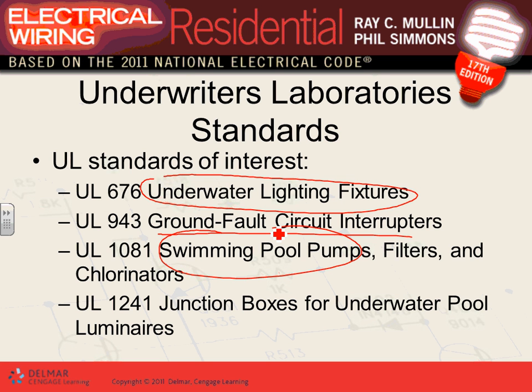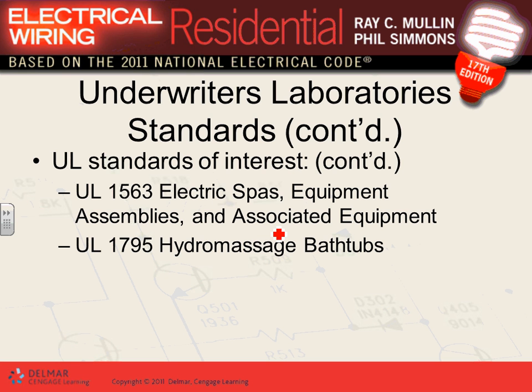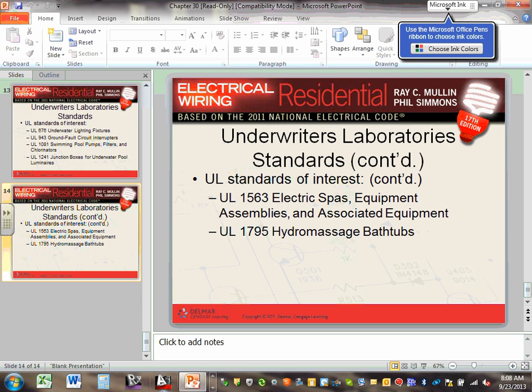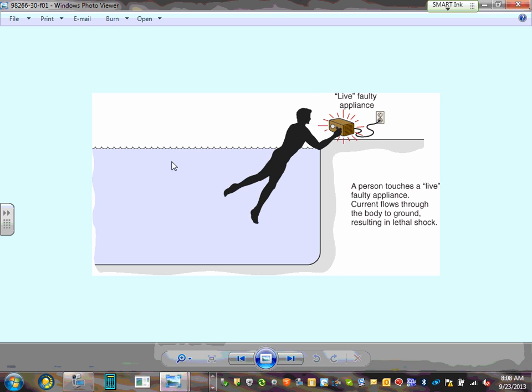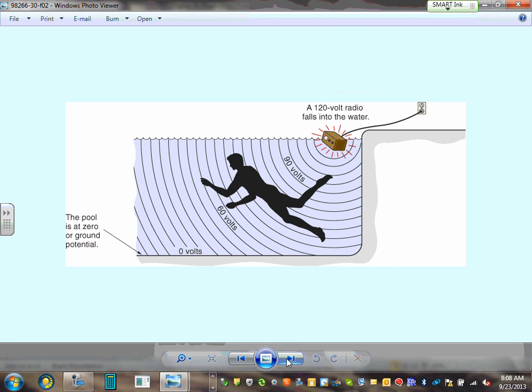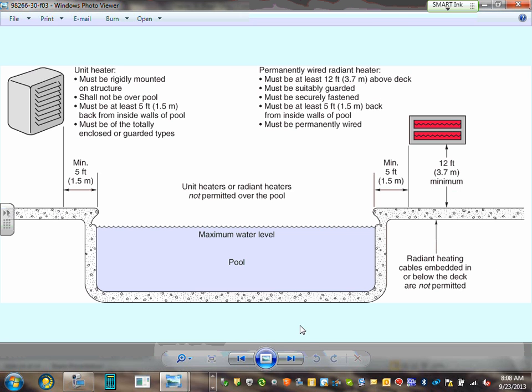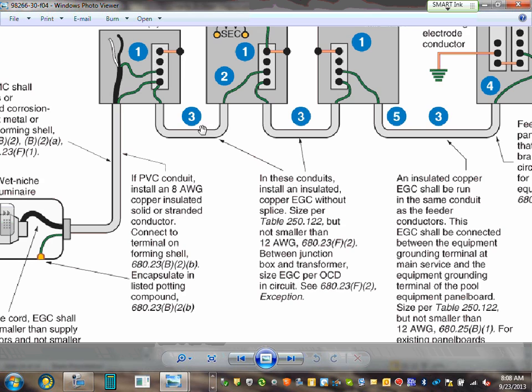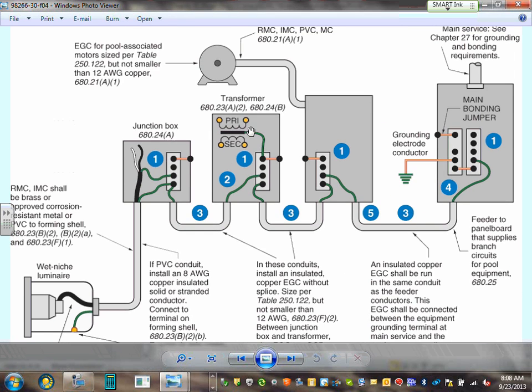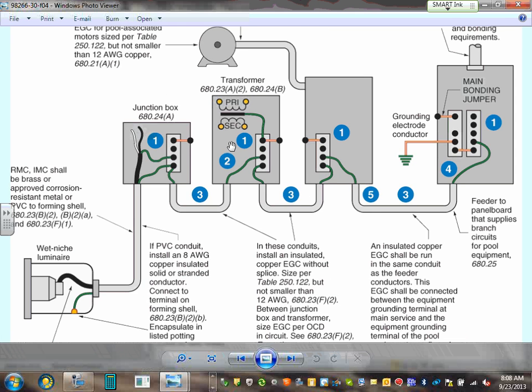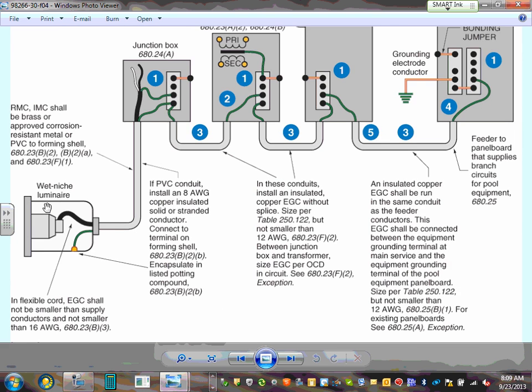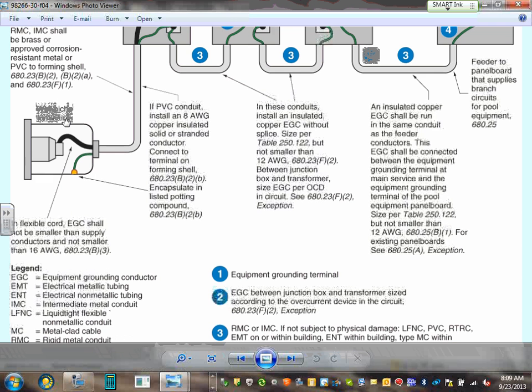Junction boxes for underwater pool luminaires: there are regulations for the type of junction box that you tap into to go to your luminaire. So these are a couple of electrical regulations for spas, hot tubs, and hydromassage bathtubs, UL regulations that govern how these equipments are listed. I want to go quick here. So we went over the electrical shock, right? Here's the gradient. We talked about the different types of heaters and the regulations. These pictures will give you the regulations for them. We talked about the grounding and pulling an equipment grounding conductor, number 12. You can see I'm feeding a transformer here, typically a low voltage isolating transformer. From the transformer you bring it to a junction box and you feed your low voltage wet niche light.